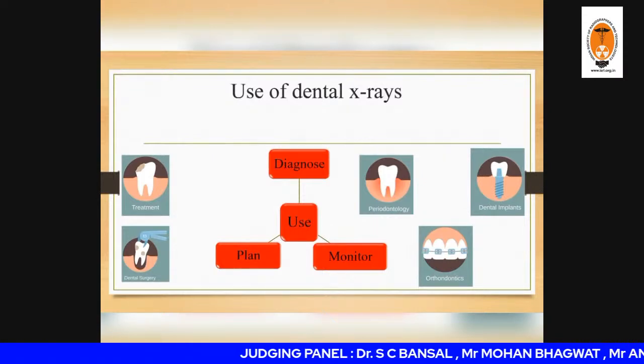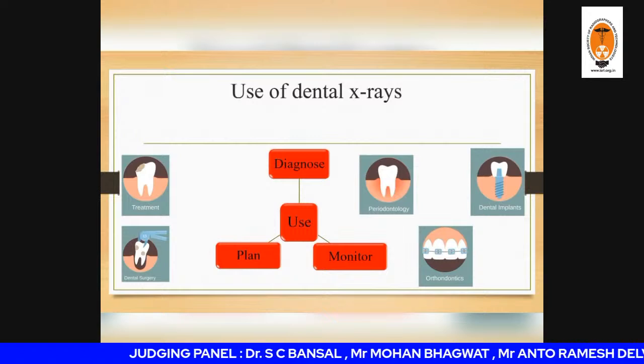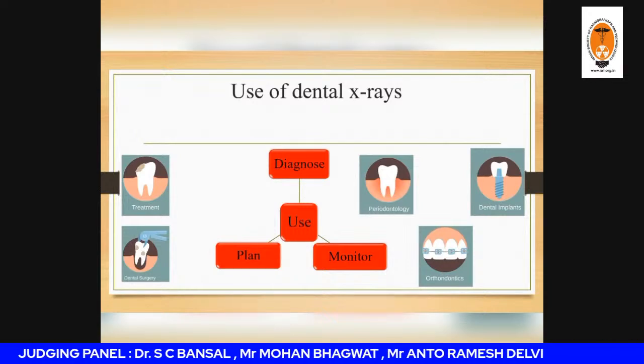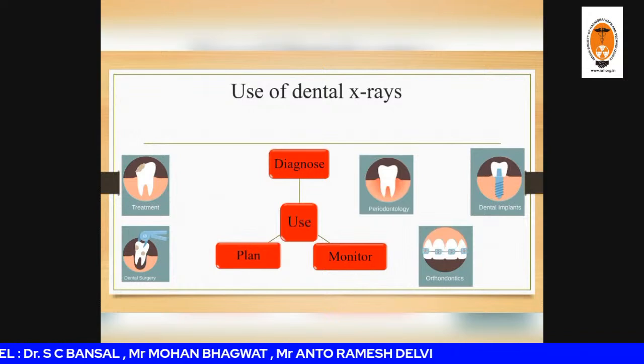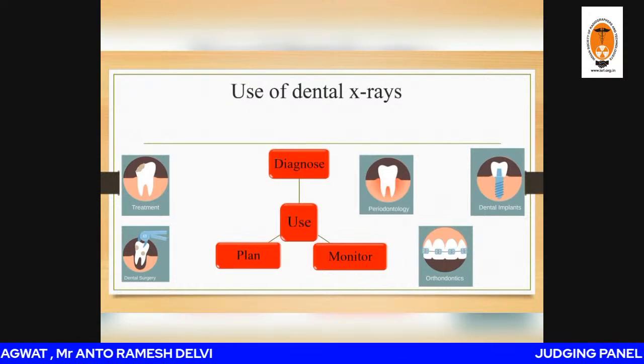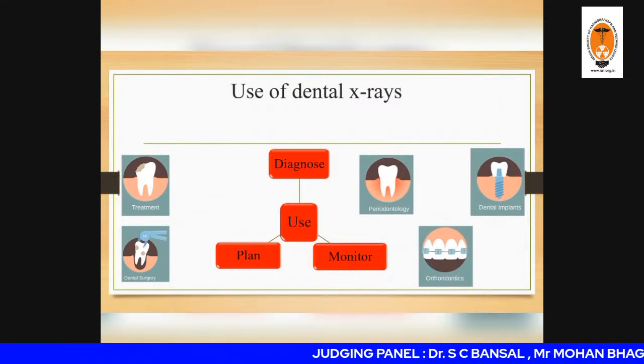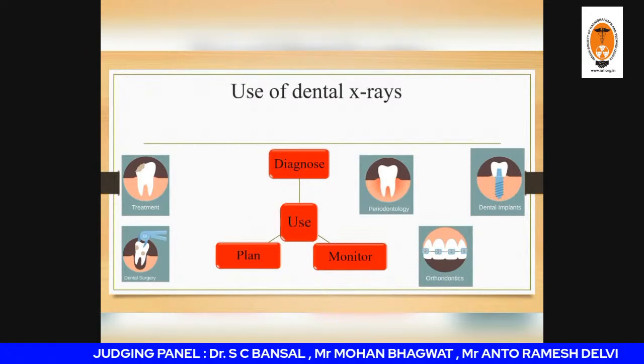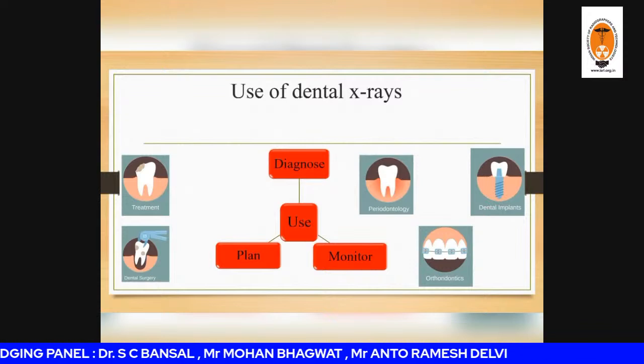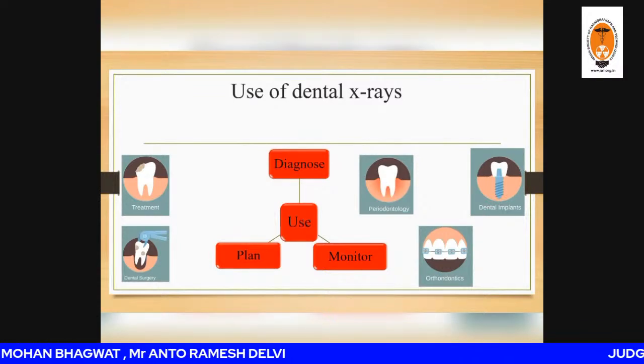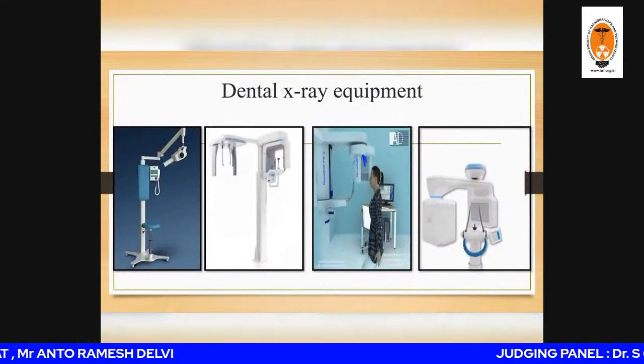The surrounding area of dental X-ray equipment must be protected from radiation to avoid exposure to persons away from the radiation source, so that the primary beam is never directed at anyone other than the patient. The patient should be positioned such that the X-ray beam is aimed at the wall of the room and not through the doors or other openings where people may be located. So for this purpose, dental X-ray room shielding must be done.